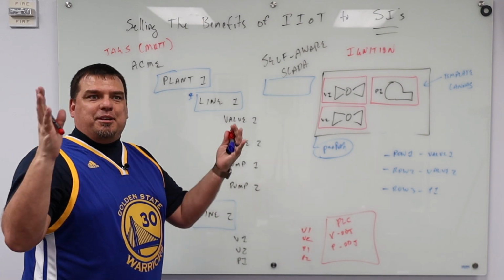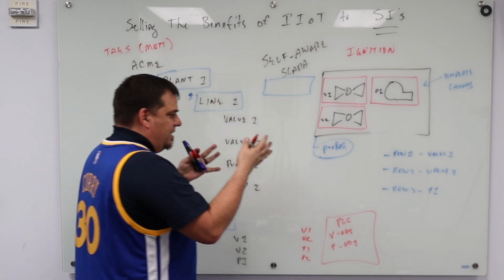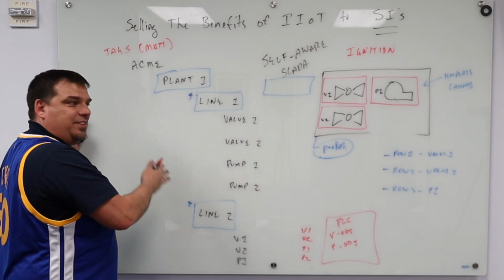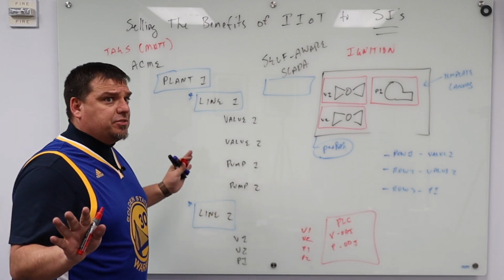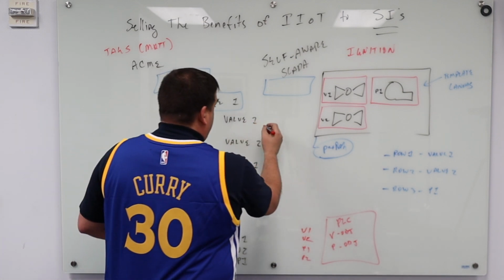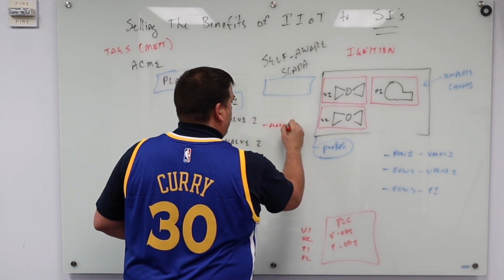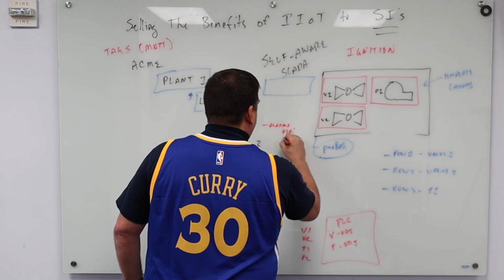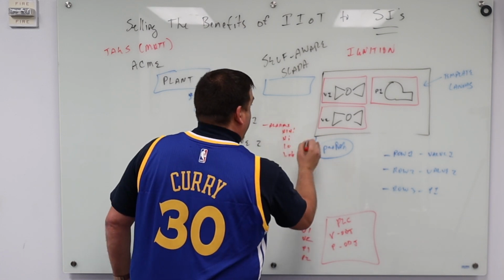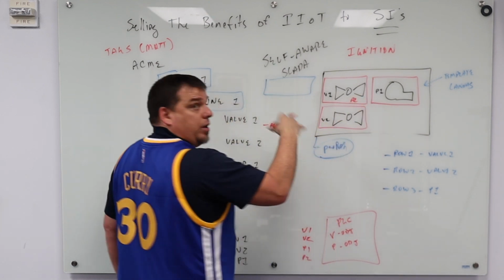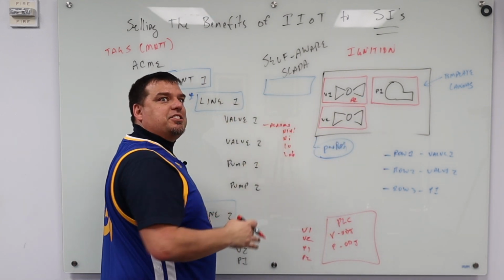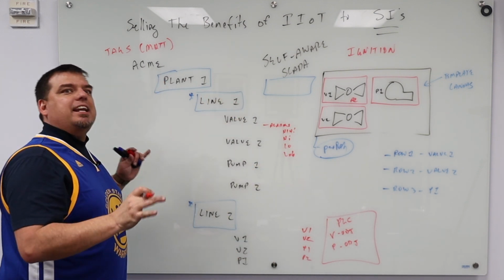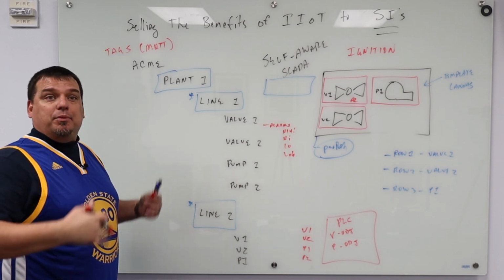So I think of the proposition for the SI as: I build the object inside my PLC that is valve, and then I make an object that lines up with my valve. And it can include lots of stuff. For example, underneath our valves, we could have a folder called alarms with high, high, high, low, low, low. And then on my template, I could right-click and go to a pop-up window that allows me to do my set points for high, high, high, low, and low, low. So I can have a fully integrated, fully dynamic self-aware SCADA system, which we've done already. We've done it many times.